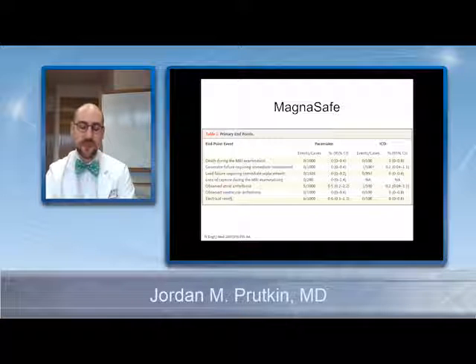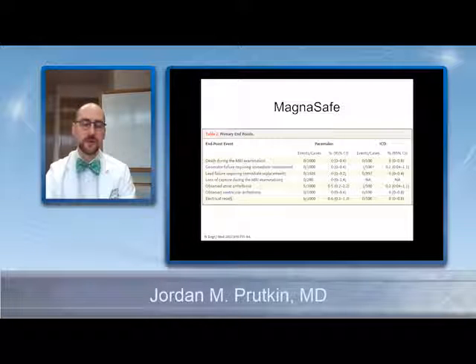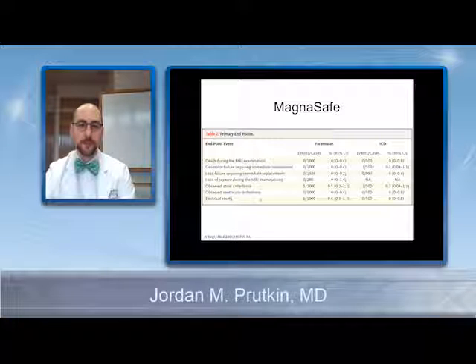And what you have to do is print out all the parameters beforehand so you have a record of it, so that if an electrical reset happens, you can make those changes back again at the end. There can be a partial electrical reset, but also a full electrical reset. And if that were to happen, which is rare, that would be one of those things where the generator failure requires immediate replacement. And again, that didn't happen in this study.